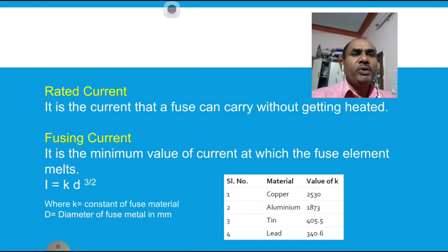For example, in this table, copper has a K value of 2530, multiplied by D, for example 1 mm or 2 mm, to the power 3/2. By calculating this value, we get the fusing current of copper wire. Similarly for aluminum, the value is 1873, multiplied by D, for example 5 mm, to the power 3/2. By calculating this value, we get the fusing current. That is the formula we already know. By substituting the K value and D value, we can find the fusing current of any metal.